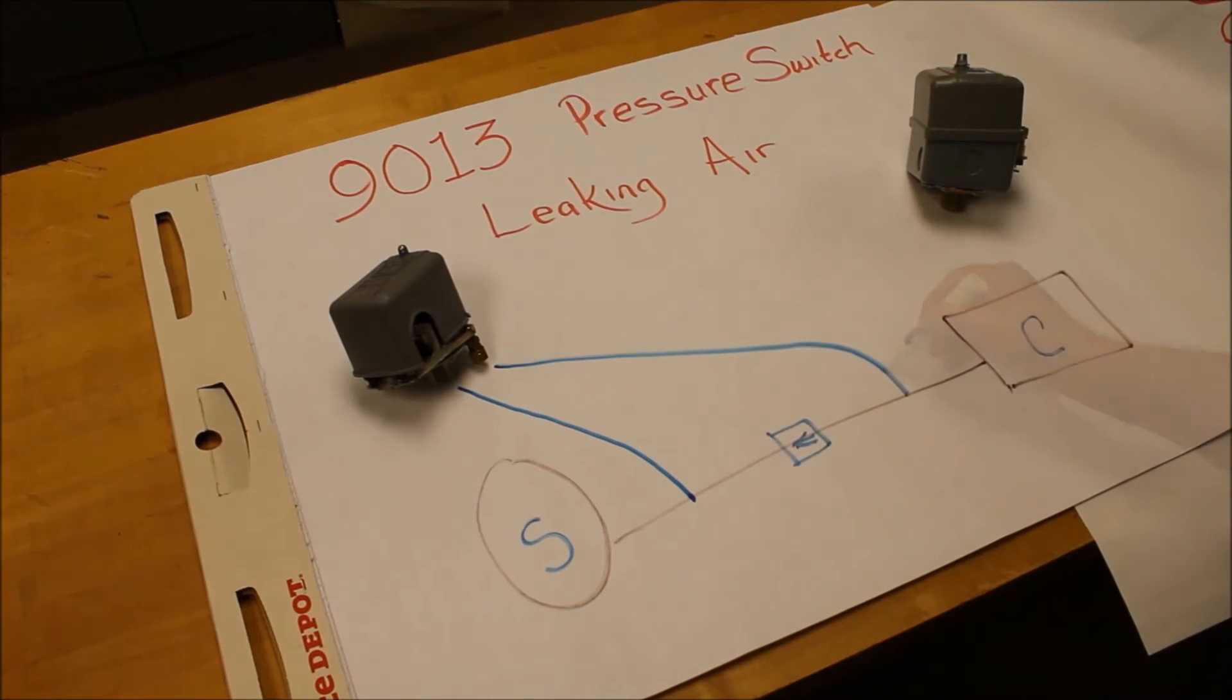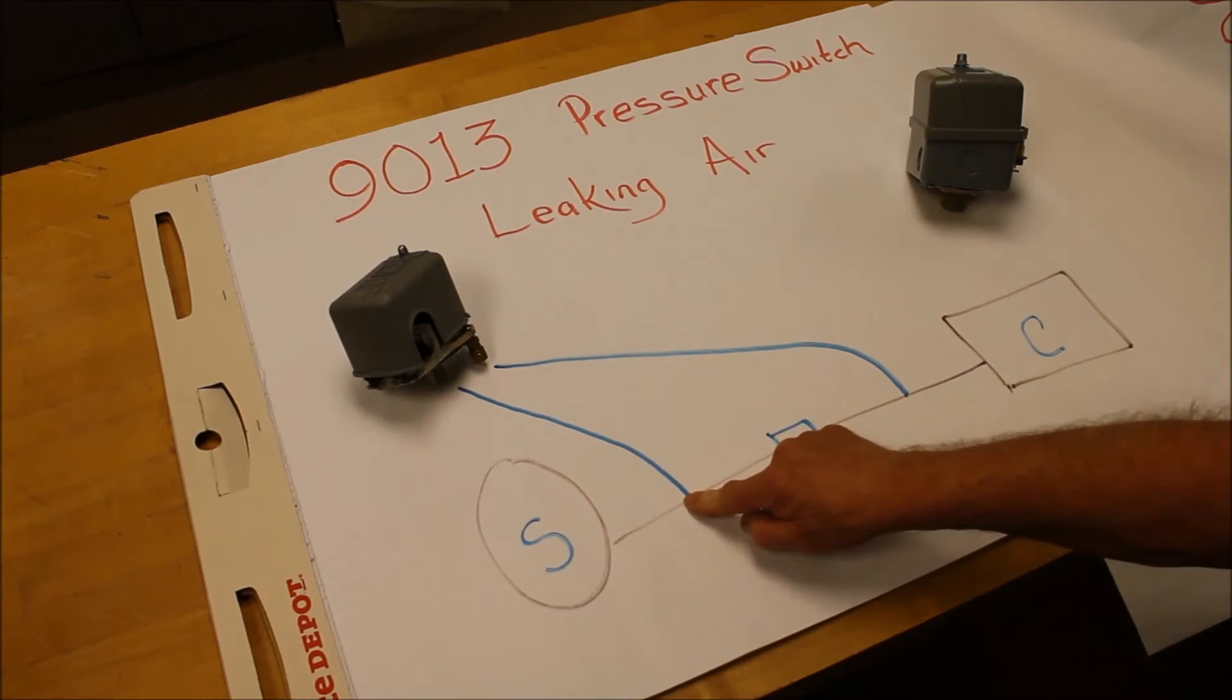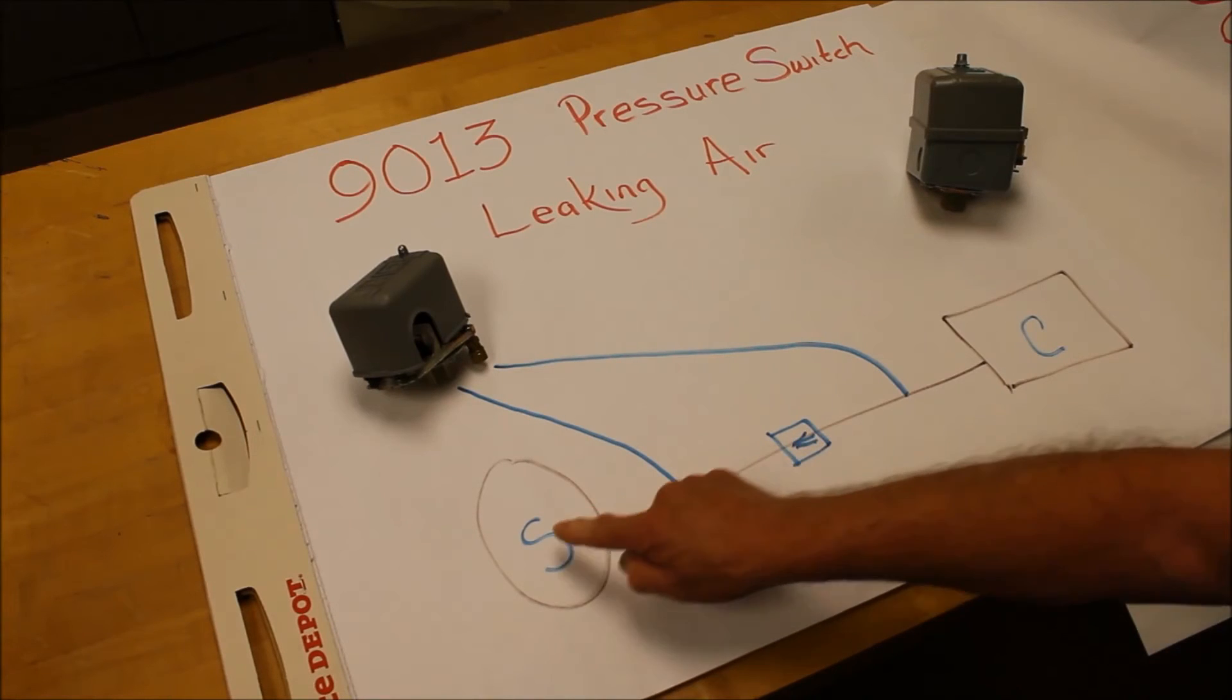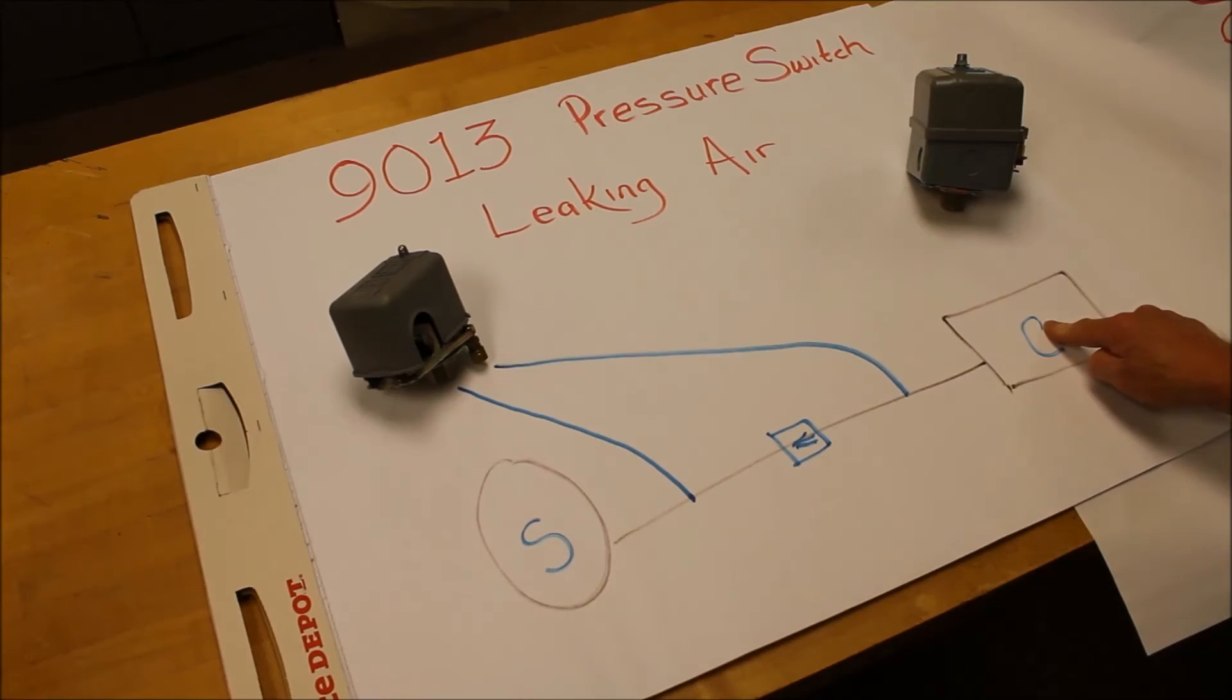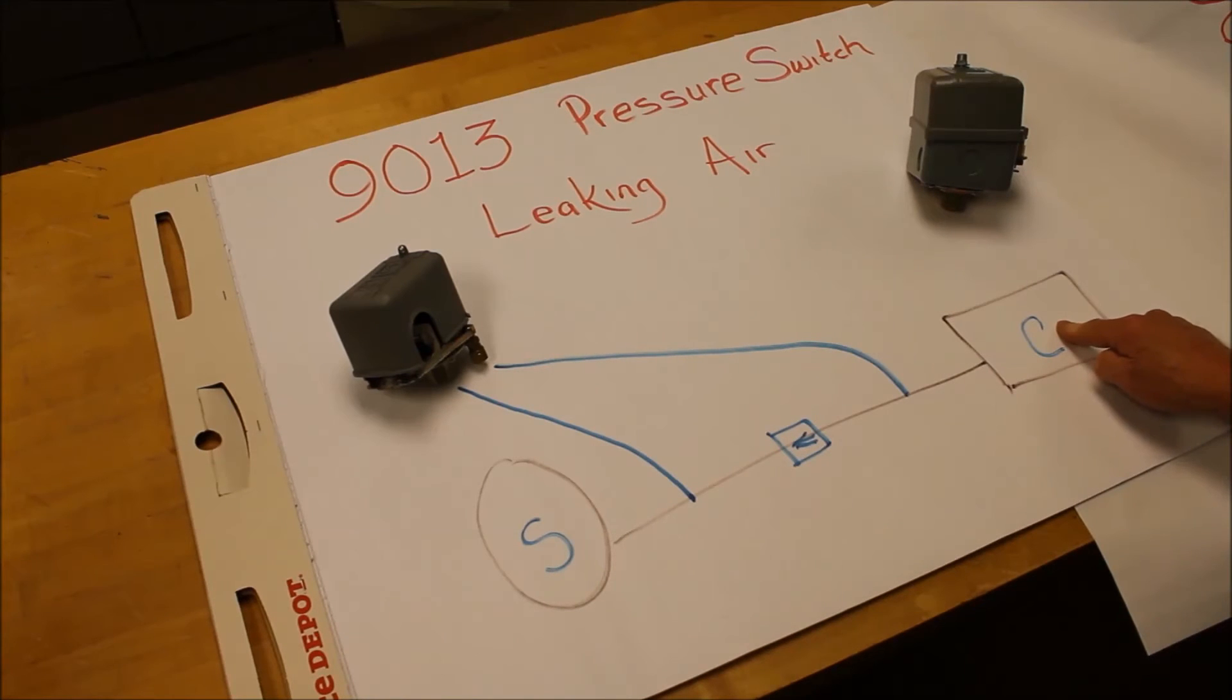The check valve must be installed between the bleed valve connection and the main pressure valve connection. If it is not, the storage tank will back feed to the compressor and you will have a constant filling of the tank and discharge until it is totally empty.